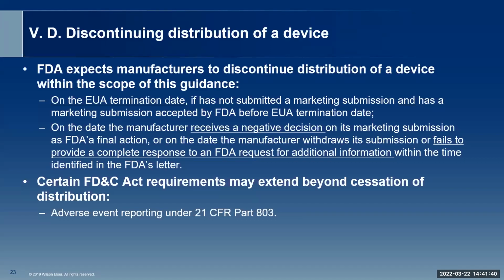The FDA also expects you to discontinue distributing your products on the date that you receive a negative decision from the FDA on your marketing submission. If the FDA rejects or denies your 510(k) application or your pre-market approval application, you must immediately discontinue your product. And also, if the FDA sends you a letter requesting additional information and you fail to provide that additional information within the time period specified in the FDA letter, you must immediately stop distributing your products.